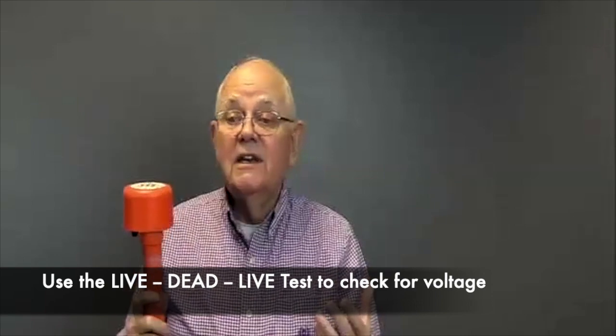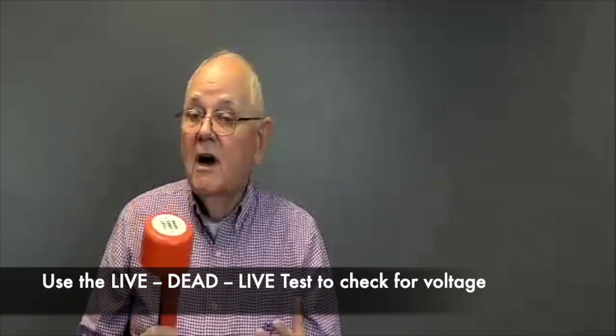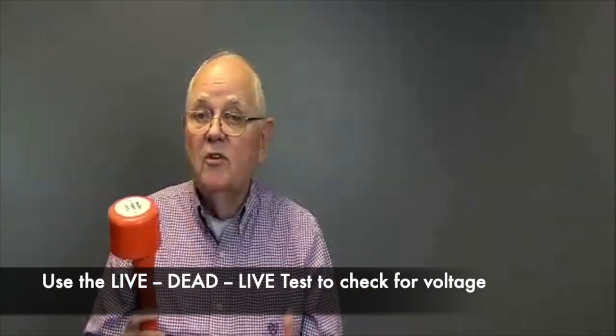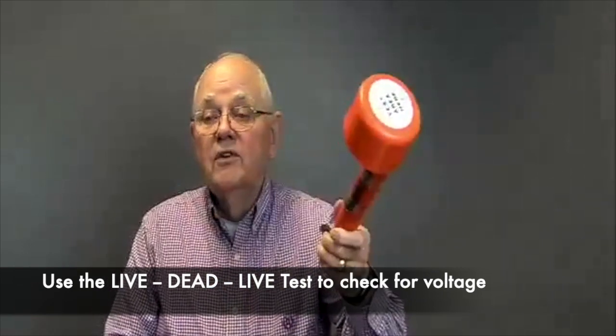Now, I have not made any contact at this point. I'm certainly not using a contact multimeter. I'm just using a voltage detector where I don't actually have to touch anything, just get close to it to see if I have voltage present or not. So in order to create that electrically safe work condition at medium voltage, I have one additional step I have to do.